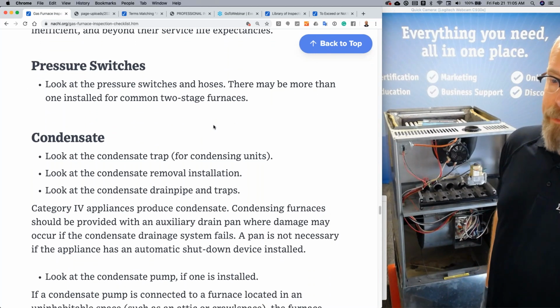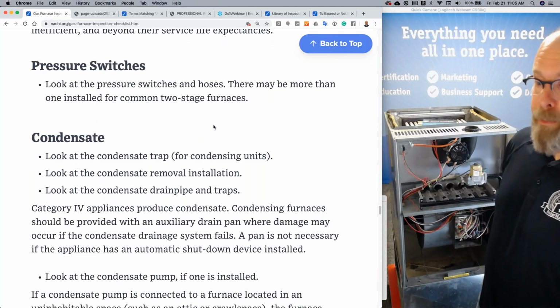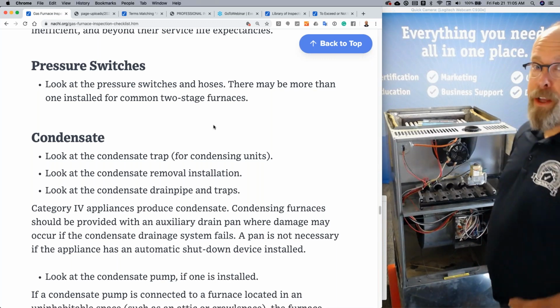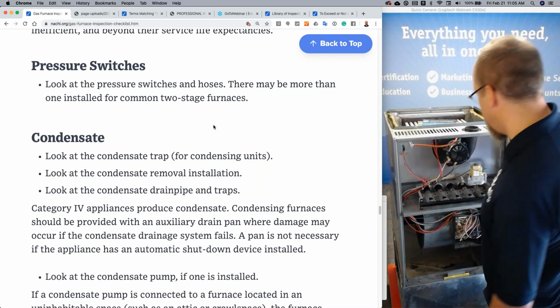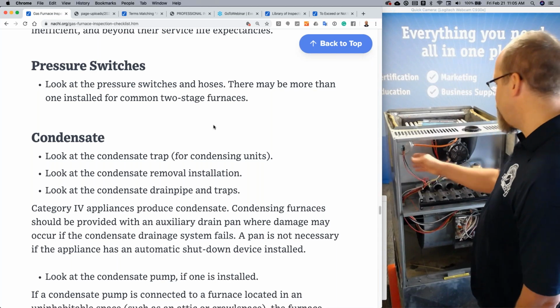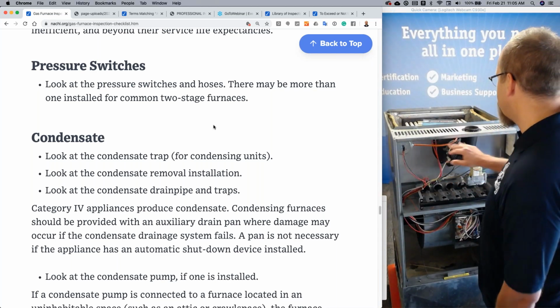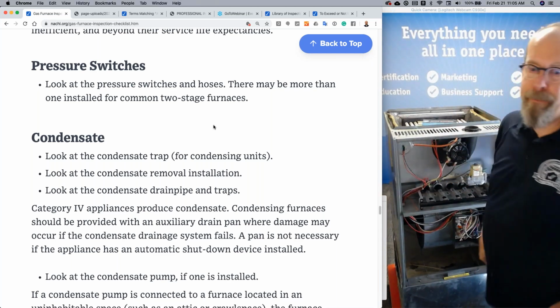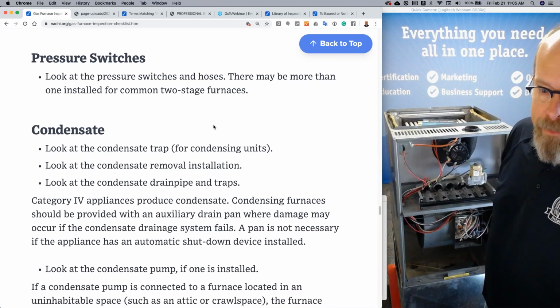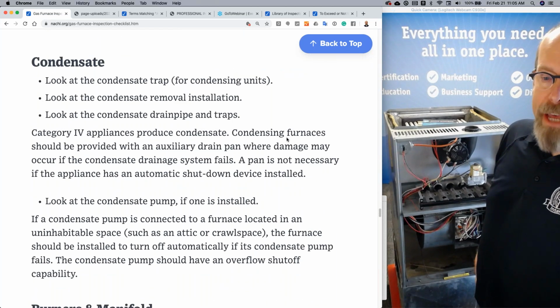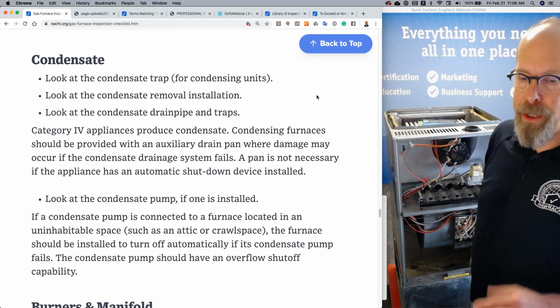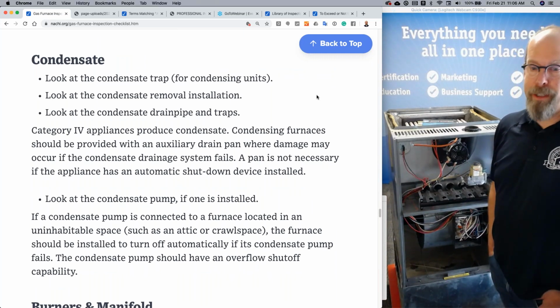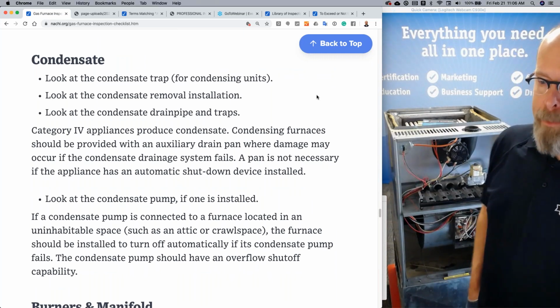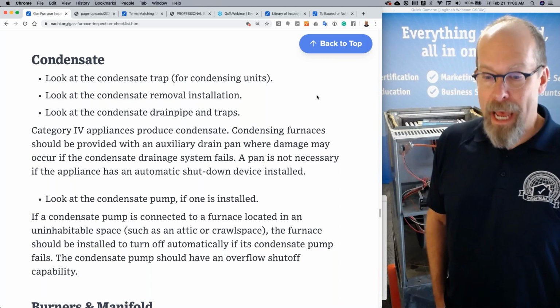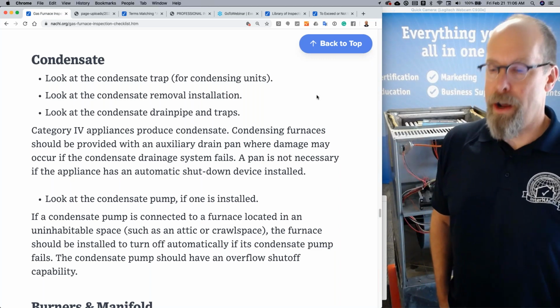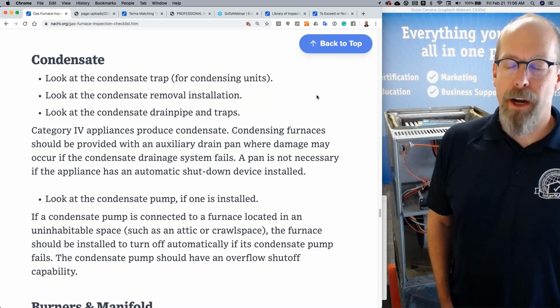Pressure switches. Look at pressure switches and hoses. There may be more than one installed on the common 2-stage furnaces. So we've got one here. There's a diaphragm, pressure hose, and there's the hose connector into the draft inducer fan. Checking the pressure. Condensate. Look at the condensate trap for condensing units. Look at the condensate removal installation. Look at the condensate drainage pipe and traps. Category 4 appliances produce condensate. That's one of the distinguishing characteristics.